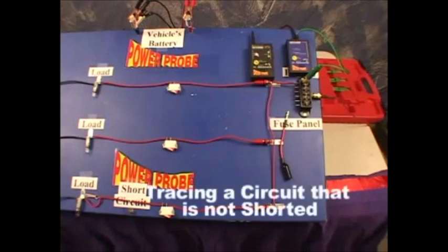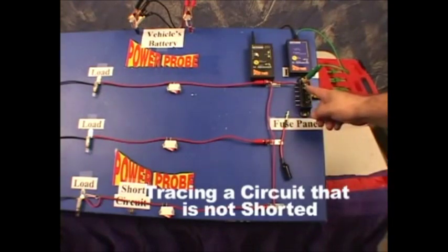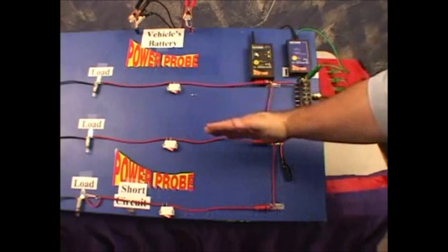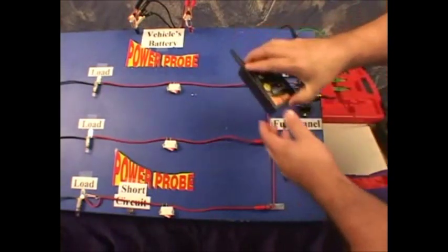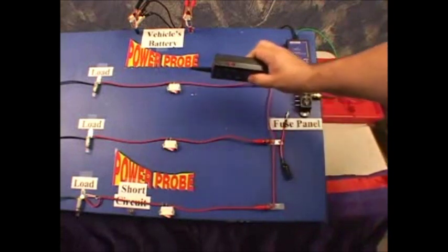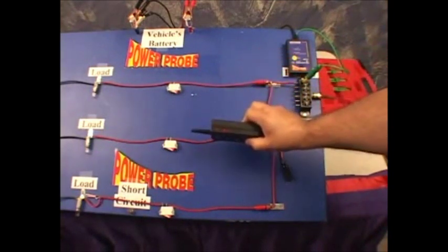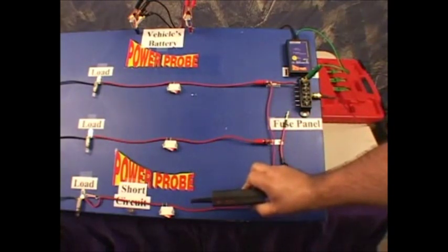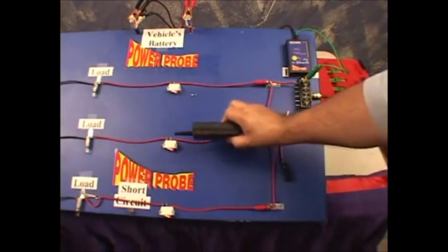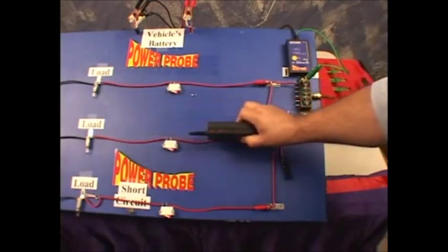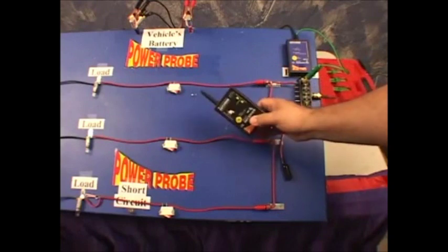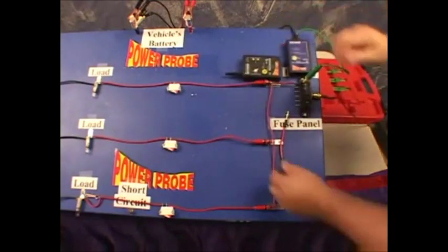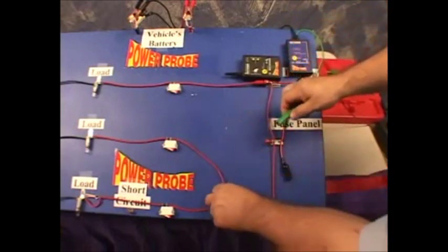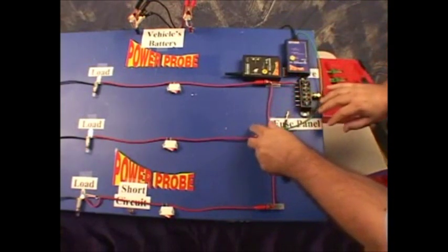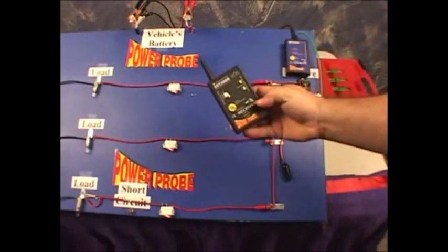The next point we're going to cover is tracing a grounded circuit that is not shorted. Here we have the signal lead connected to the fuse terminal of a parallel circuit with 3 branches. Let's turn on the smart receiver. We need to understand that since this parallel circuit is not shorted, it will have signals of equal strength along each branch. This can make it very confusing to have signals transmitting down circuits you do not want to trace. Let's say you want to trace the middle circuit and not be confused by the other branches. You have to isolate the circuit you're tracing and connect the signal lead exclusively up to it. Take the smart receiver and lock in the sensitivity.